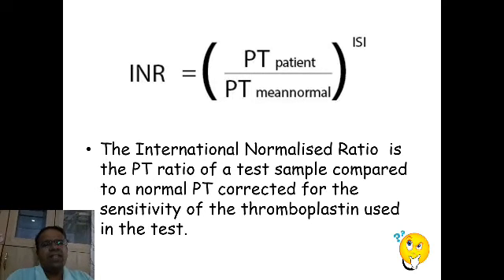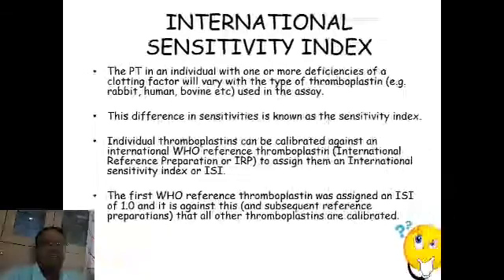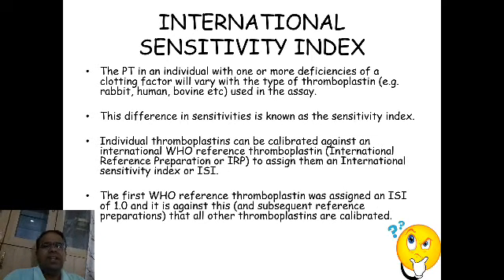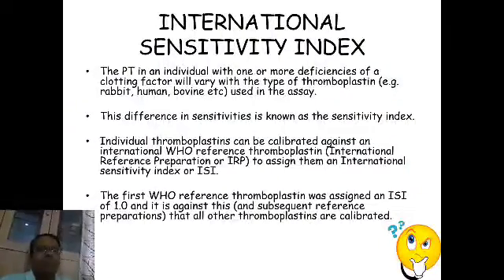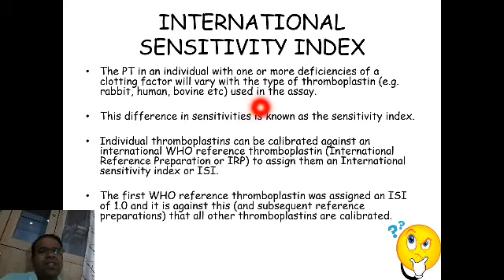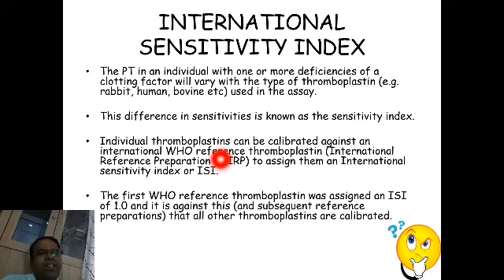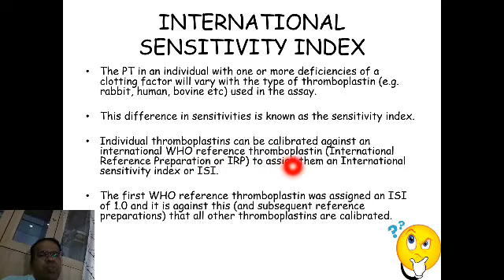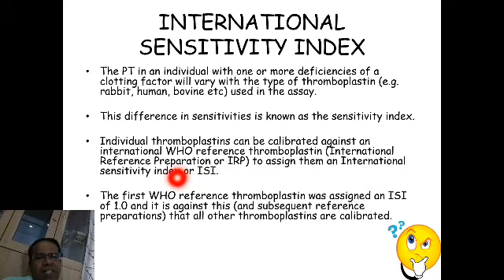ISI is the international sensitivity index. The concept arose because the PT in an individual with one or more clotting factor deficiencies will vary with the type of thromboplastin used in the assay — for example, whether it is rabbit, human, bovine, or otherwise. This difference in sensitivities is known as the sensitivity index. Individual thromboplastins (the prothrombin reagent) should be calibrated by manufacturers against the international WHO reference thromboplastin, also called the international reference preparation (IRP), to assign them an ISI.